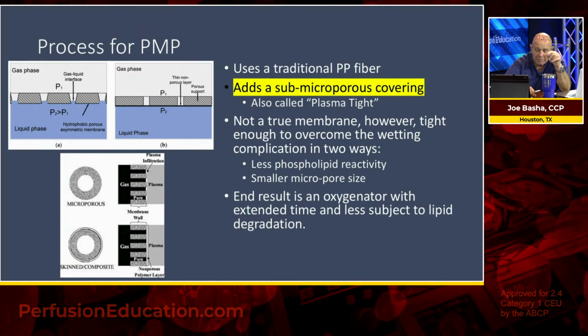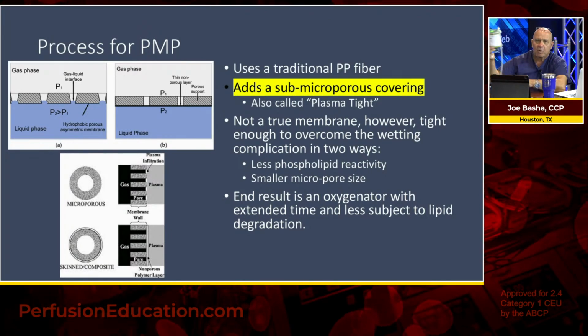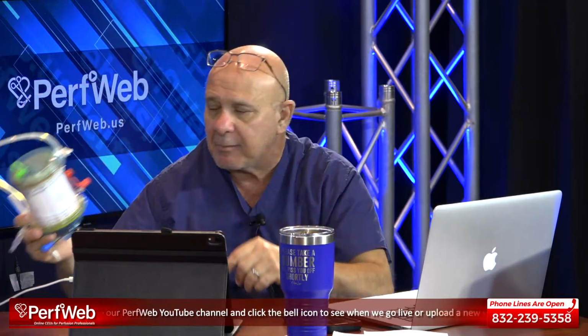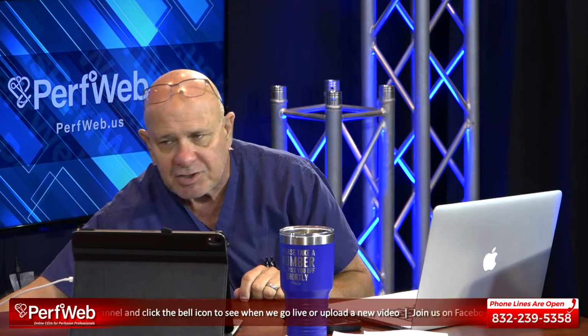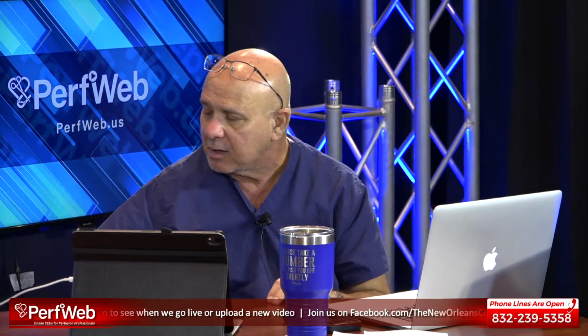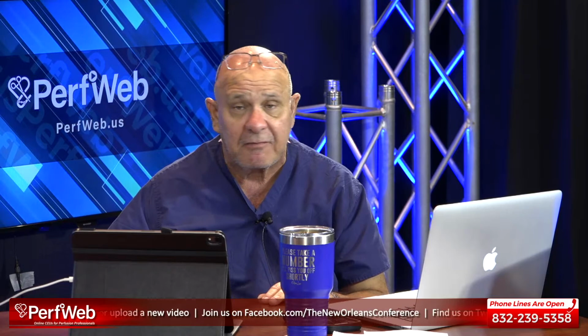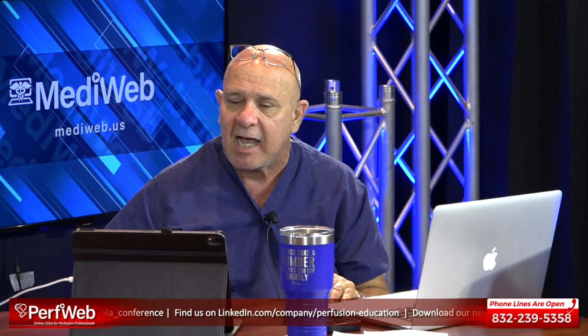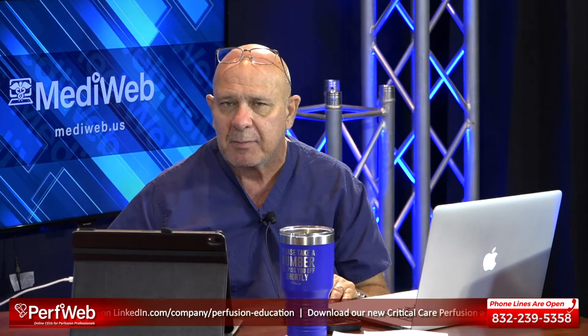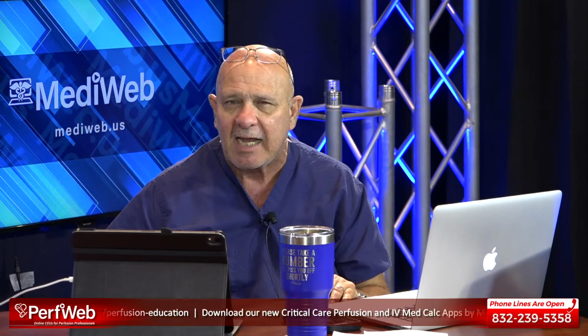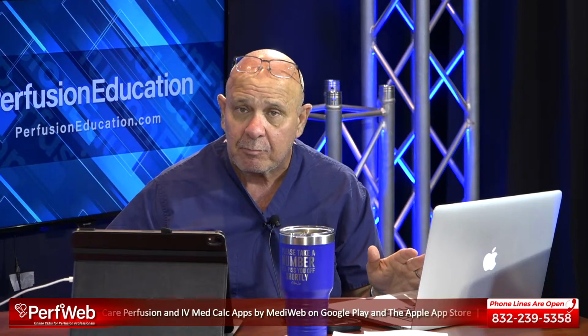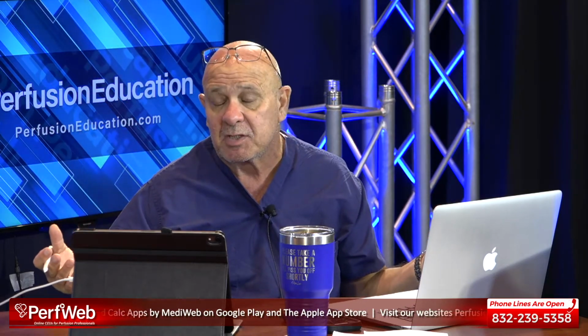But there's one manufacturer, it's 3M. So this one's made from that fiber. The Quadrox, the square oxygenator, is made from that fiber. I believe the tandem oxygenator, the one with no heat exchanger, is made from that fiber. I know that the MC3 is made from that fiber, the one that Medtronic distributes for Dr. Bartlett's company. I'm assuming, I don't know for sure, that the Abiomed ECMO oxygenator that they have is also PMP. I would think that not too many people are going to use polypropylene in a design like that today. But polypropylene oxygenators will continue to exist because they're great for on bypass, and they're much more affordable.